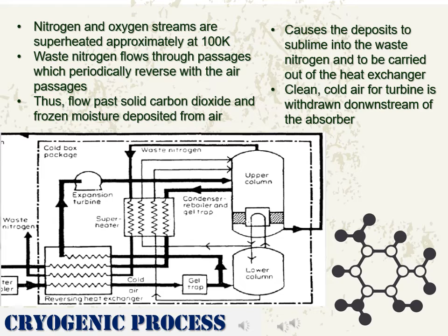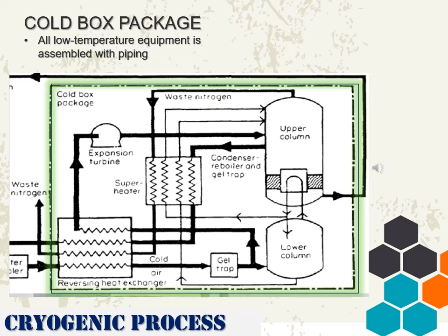By expanding a portion of the air stream through a centrifugal expansion turbine, refrigeration to overcome heat influx in the process is provided. Reheated in separate passages of the reversing heat exchanger to the proper temperature. To help maintain clean operation of the reversing heat exchanger, reheating serves to control the temperature pattern. Air exhausting from the turbine is fed to the proper tray of the upper column. This is the cold box package where all low temperature equipment is assembled with piping.